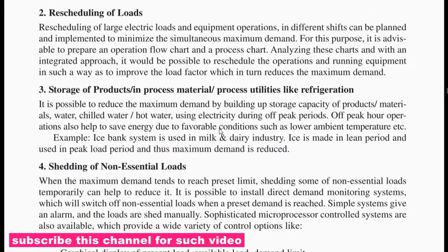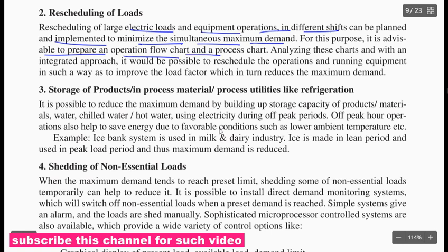Rescheduling of load. Rescheduling of large electrical loads and equipment operation into different shifts can be planned and implemented to minimize the simultaneous maximum demand. For this purpose, it is advisable to prepare operation flow charts and process charts and analyze these charts. With an integrated approach, it should be possible to reschedule the operation and running of equipment in such a way as to improve the load factor, which in turn reduces the maximum demand.